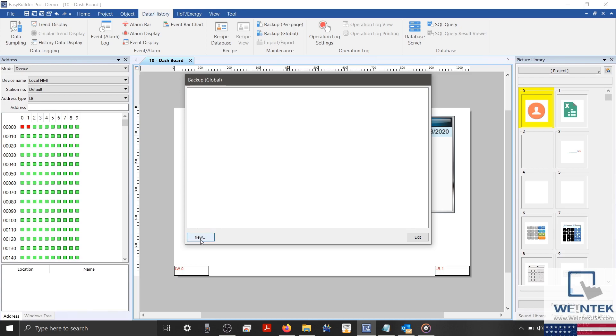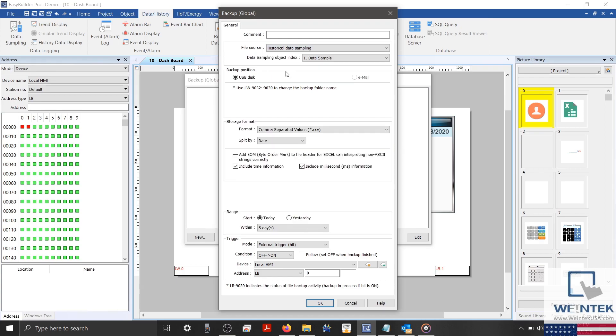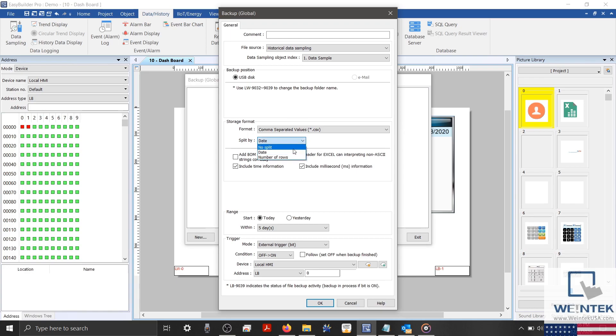Within the following dialog, I'll select New on the bottom left, and within our Backup Object Settings, I'm going to select Historical Data Sampling as my file source. In the Object Index drop-down list, I'll ensure that the Data Sampling object that I'd like to export is selected. Our storage format is set to CSV, and in this demonstration, all of our data sampled will be saved into one file called Data. By setting our Split By format to Date, our sampled data will be split according to the date in which the data was recorded. This is a great way to keep your data organized, but if this format does not fit the requirements of your application, you may also choose to export all records to a single CSV or split them by number of rows.